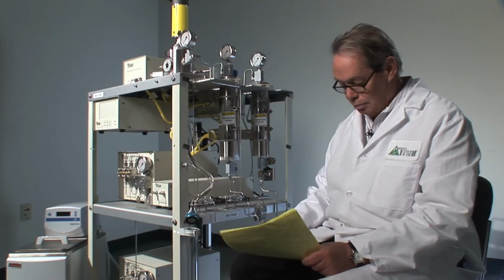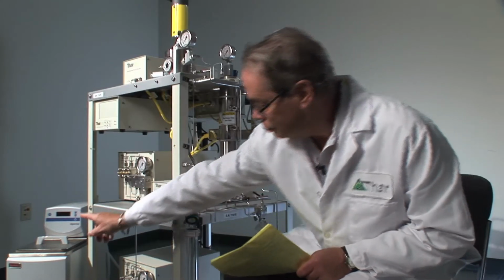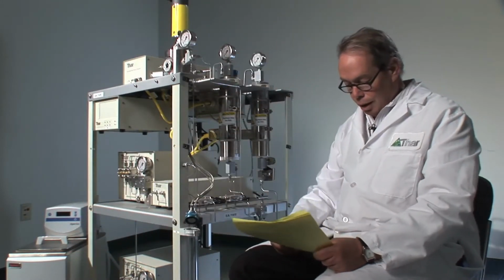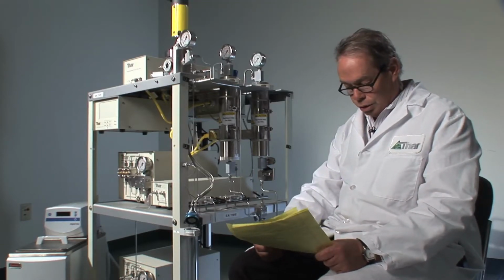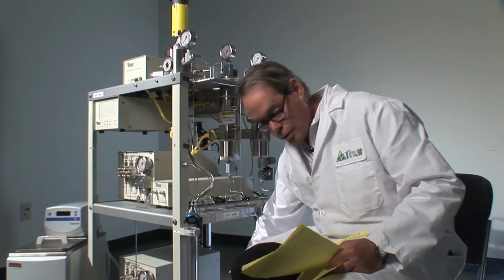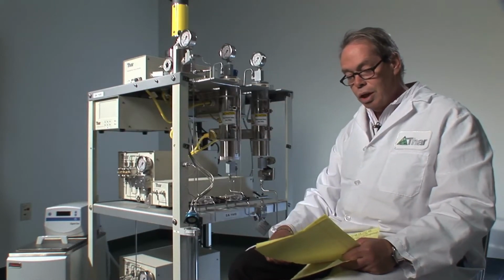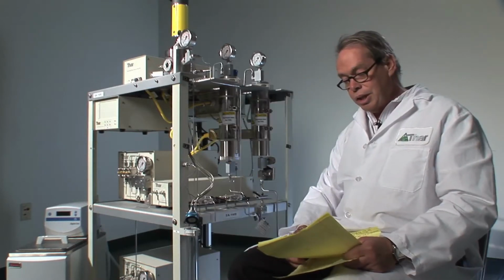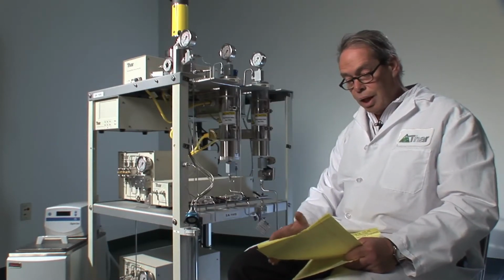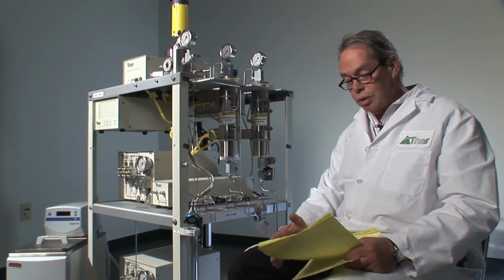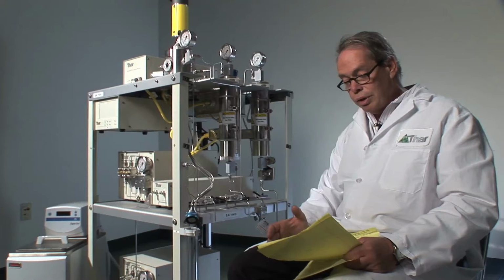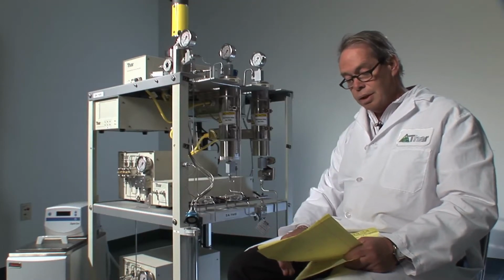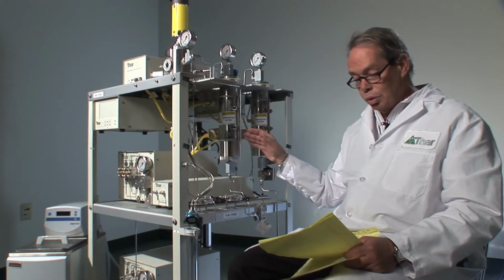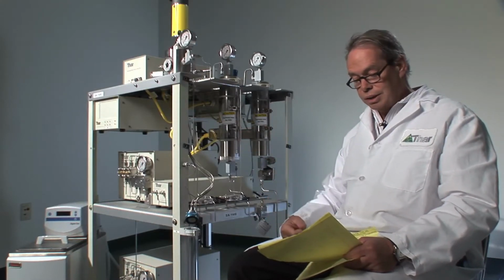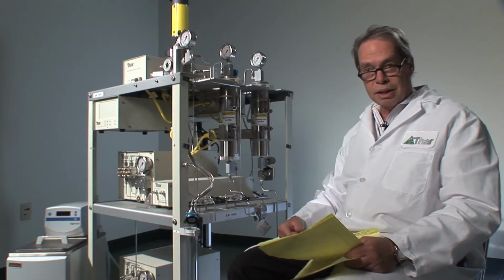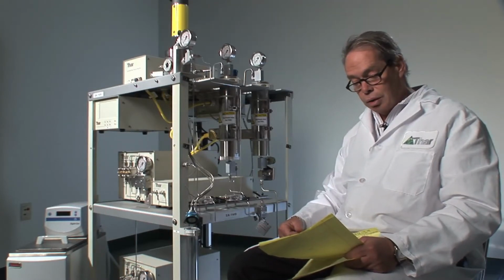Components of the extraction system include the recirculating chiller. This provides chilled ethylene glycol solution to the heat exchanger. The heat exchanger cools the CO2 before it goes to the pump. When the CO2 reaches the pump, it is a liquid, allowing the pump to deliver denser CO2, and it cools the pump, reducing pump head cavitation. The chilled CO2 is delivered to the dual-headed CO2 pump that pressurizes the CO2. Its maximum flow capacity is 50 ml/minute of liquid CO2.